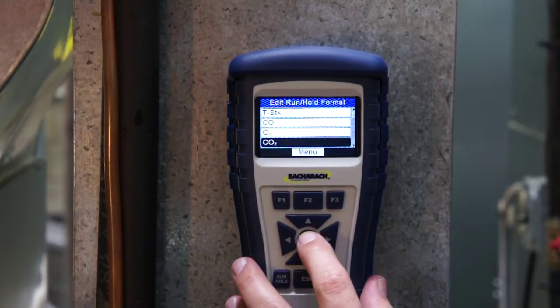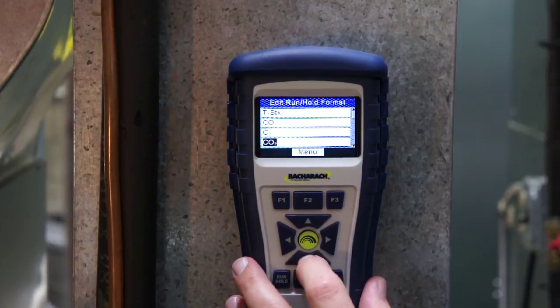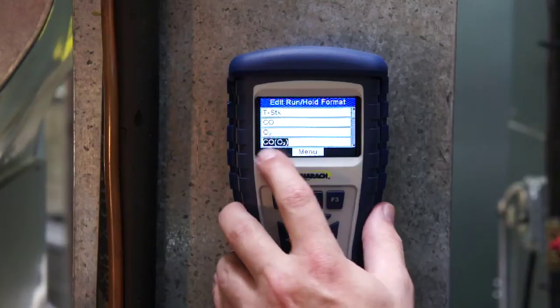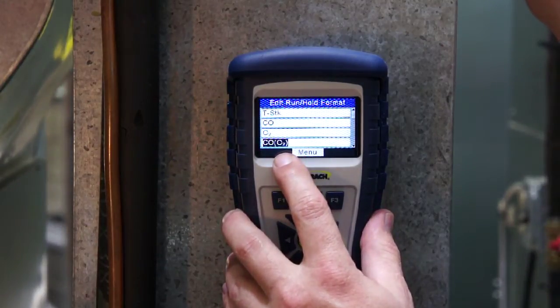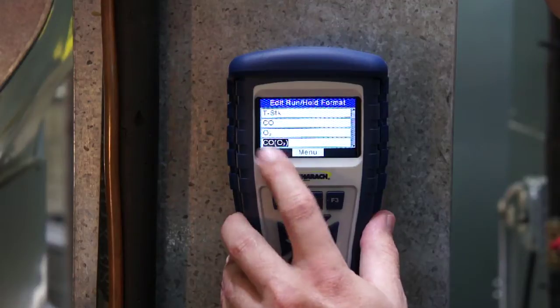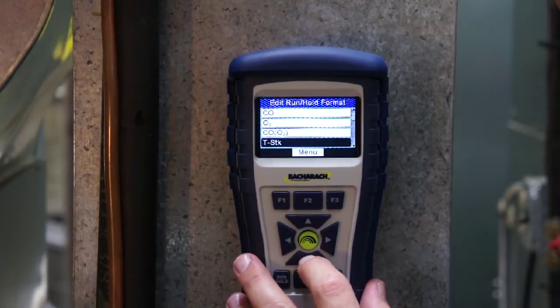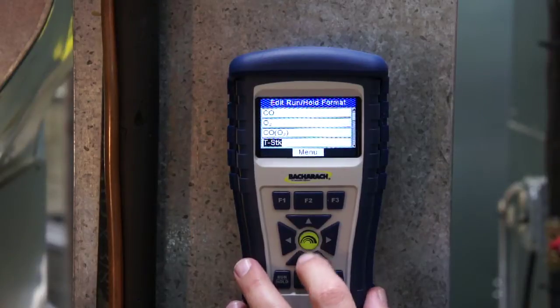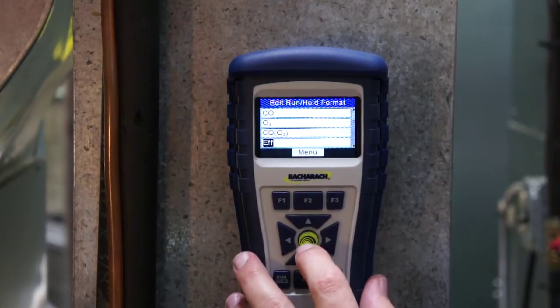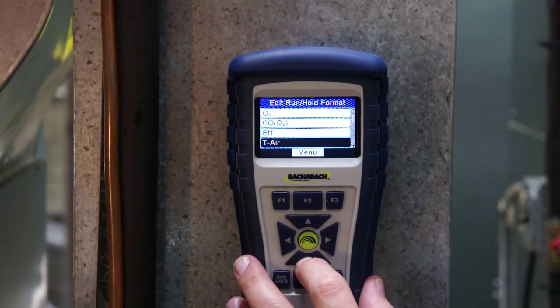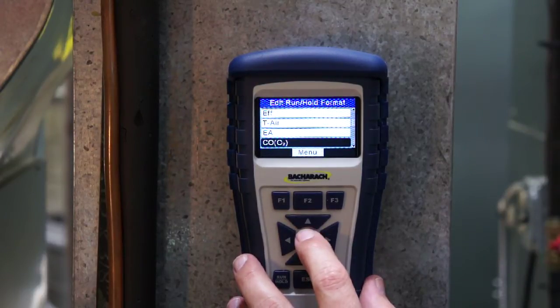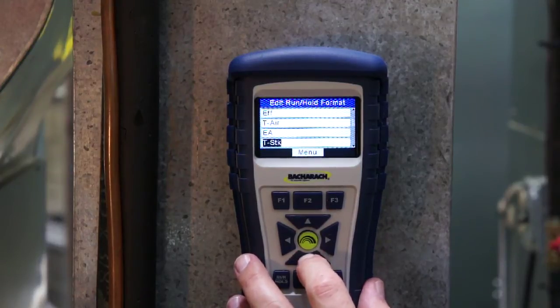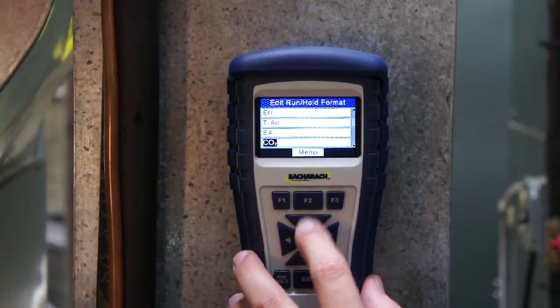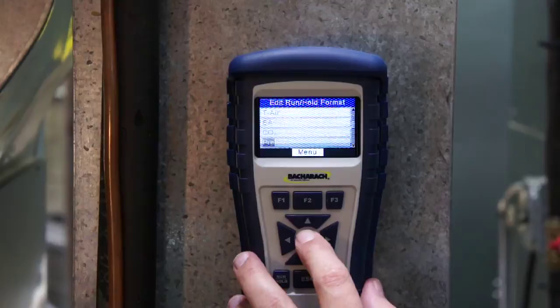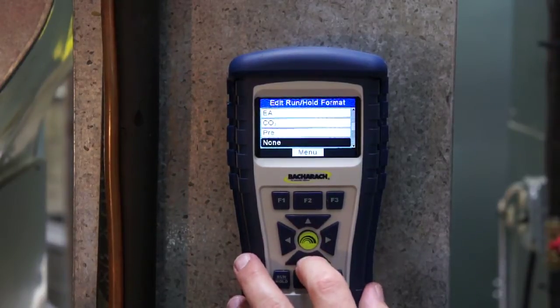And then maybe I want here CO air free, hit enter. And you're going to see this come up a little different. This is actually CO with respect to oxygen. So it's same thing, CO air free or CO undiluted. It's a calculated value, hit enter. And then scroll down again. Now we already have temperature stack in there, so maybe I want to show my efficiency here. Scroll back up, hit efficiency, and then I got the temperature of the air, the excess air, and here's my CO corrected, so undiluted. So I'll put down here, what else do we have left? CO2. CO2, enter, and then I got pre, which is my pressure, enter, and then to none.